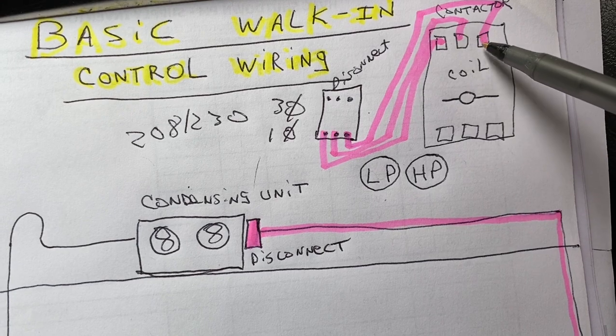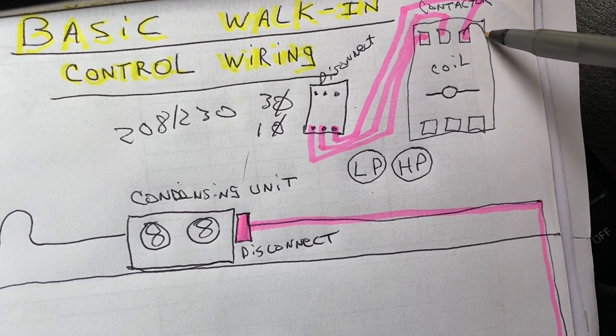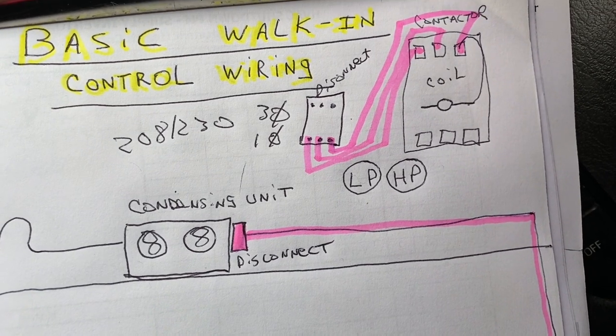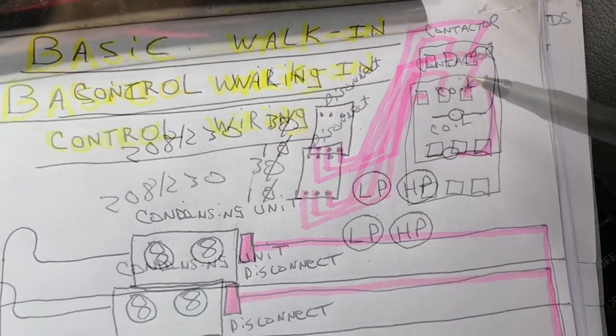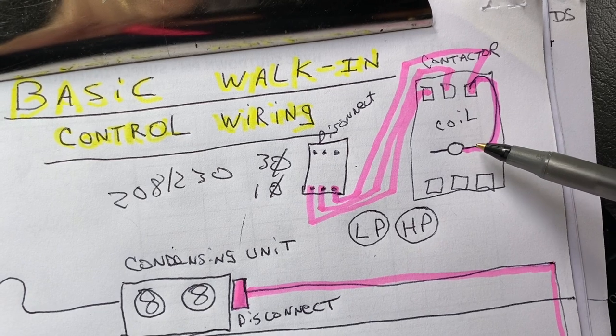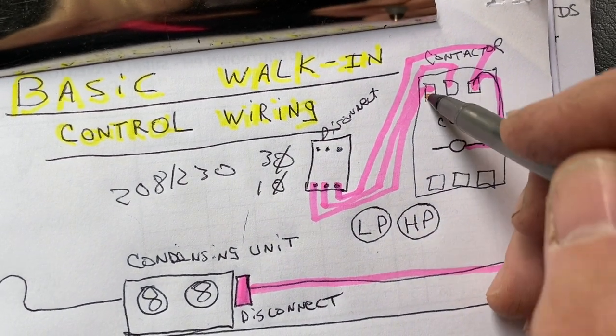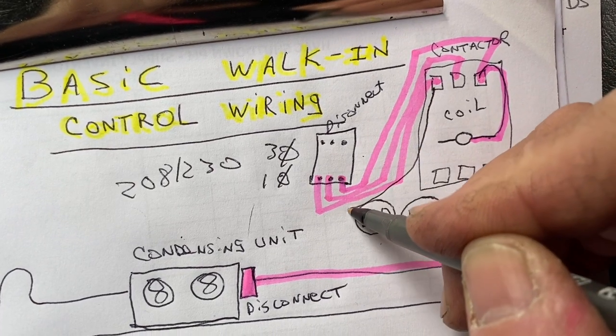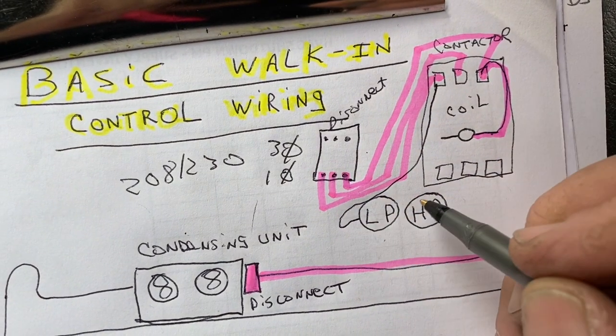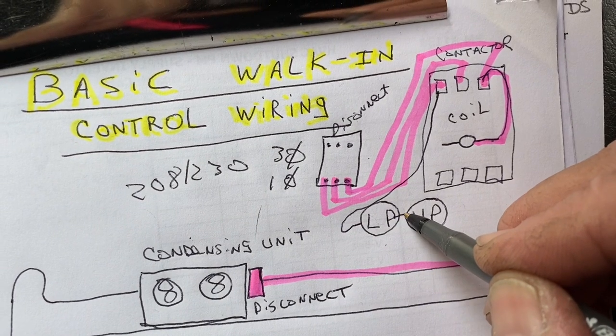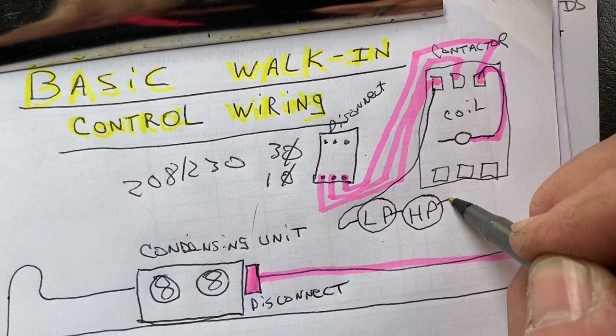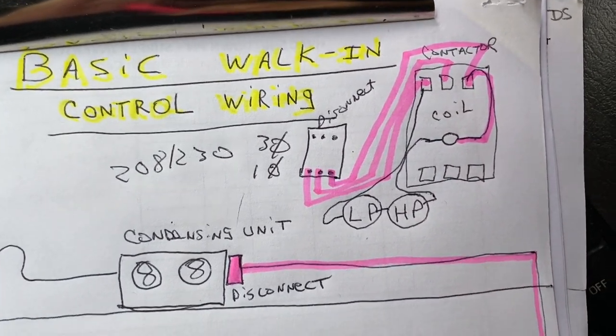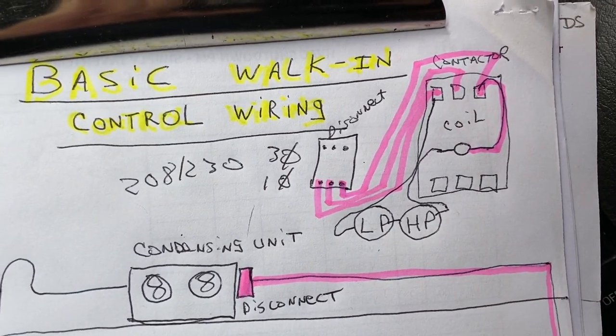So let's get those going next. Your coil in your contactor is right here. It's usually a 240 volt coil. Usually what we do is we just take one leg to half of the coil. That's how they do it. It's that simple. So we got that drawn in there. Half of the coil is fired off. Then we'll take one other leg through the low pressure control, through the high pressure control, and back to the other half of the coil.